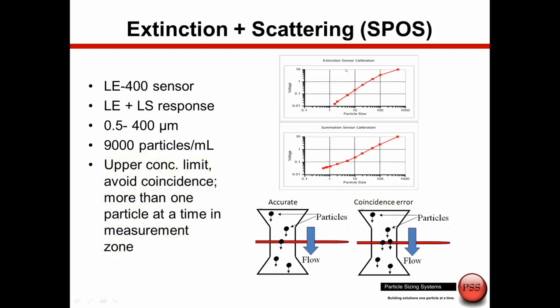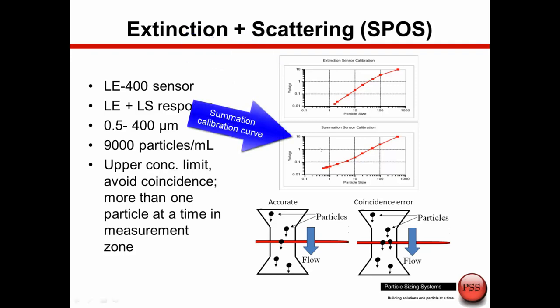What we see here are calibration curves. This is a calibration curve using only the extinction detector, which we may use for applications where we don't need to measure down to 0.5 microns. And this is a calibration curve for the summation mode where we use both extinction and scattering detectors.